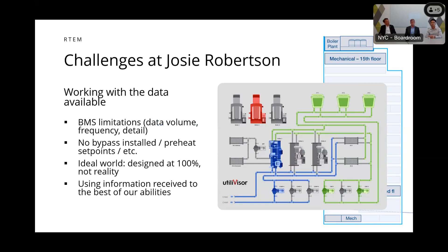So some of the successes that we had implementing RTEM in our facility was we were able to reduce the condenser approach. We found that our maintenance was lacking in a sense. So we were able to increase our cooling tower maintenance and our sand filter maintenance, and we were able to bring down our condenser approach from 6 degrees to 1 degree.